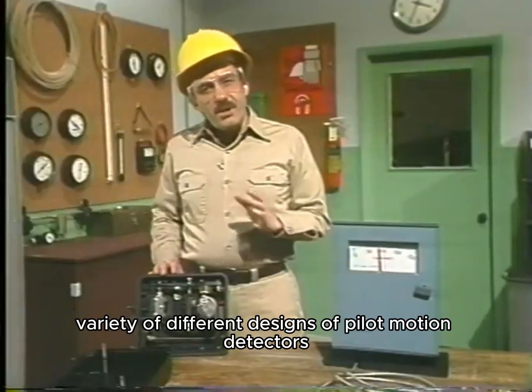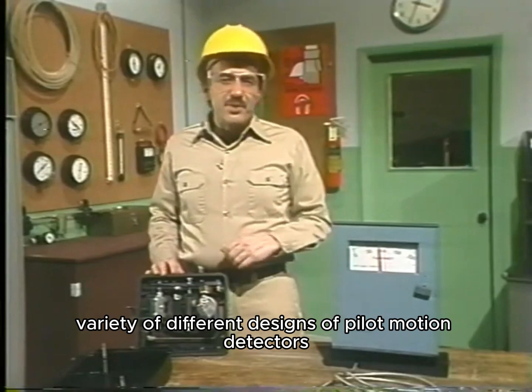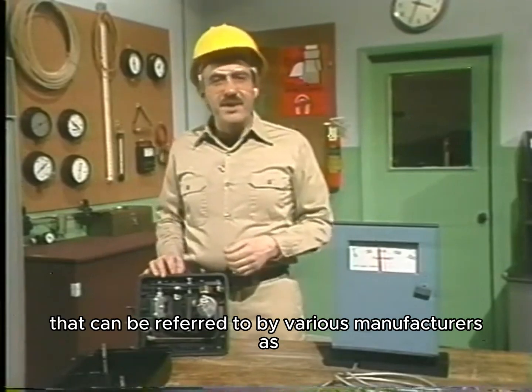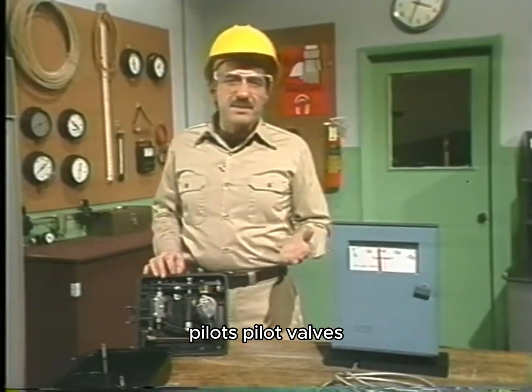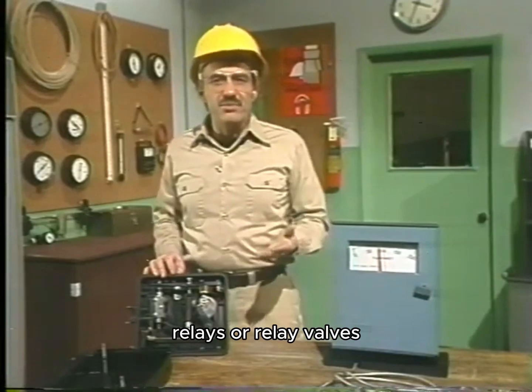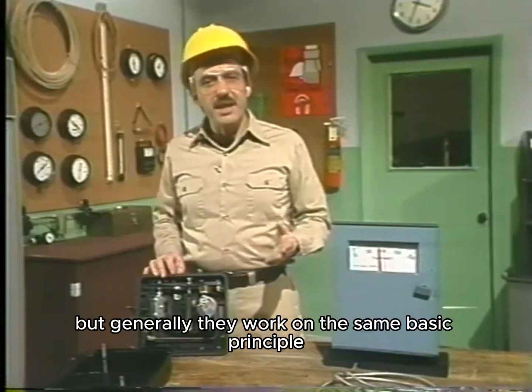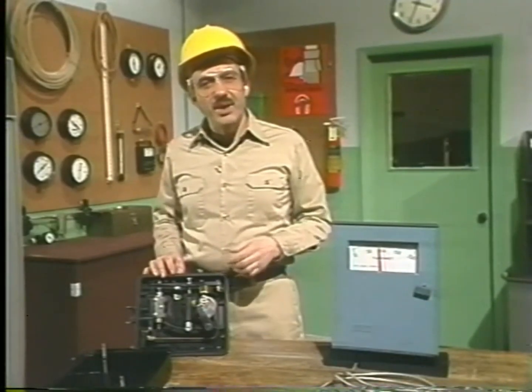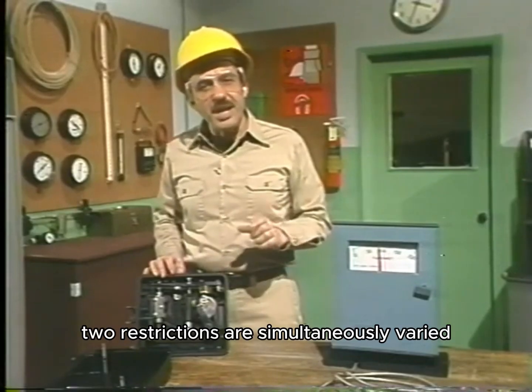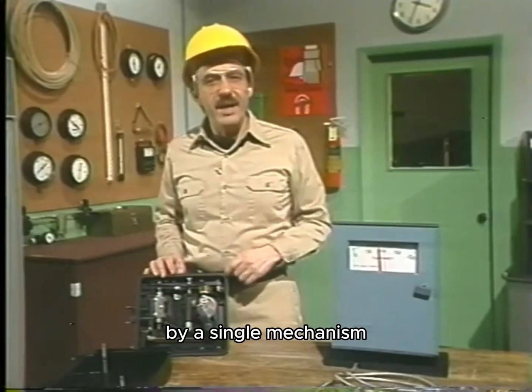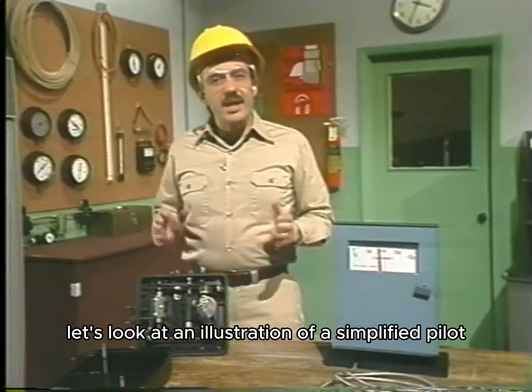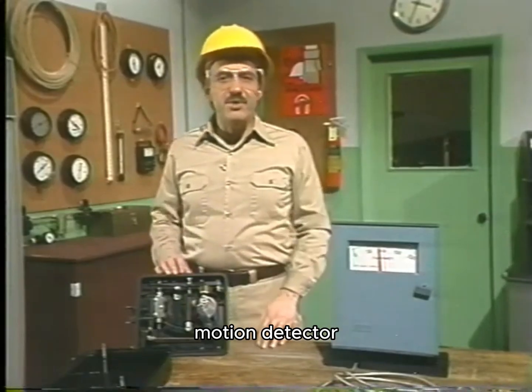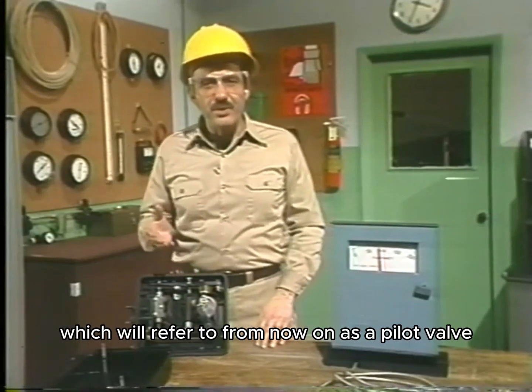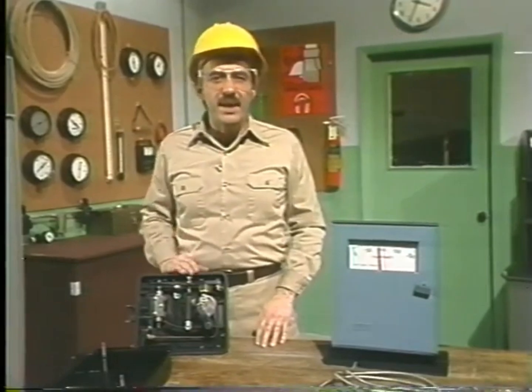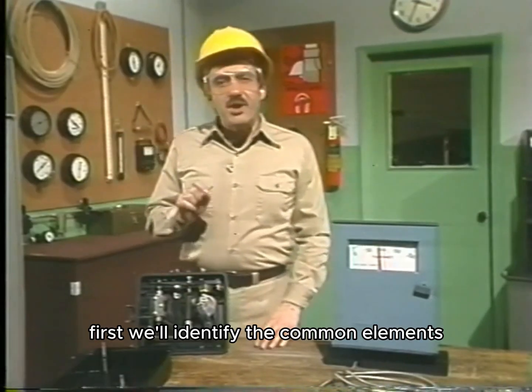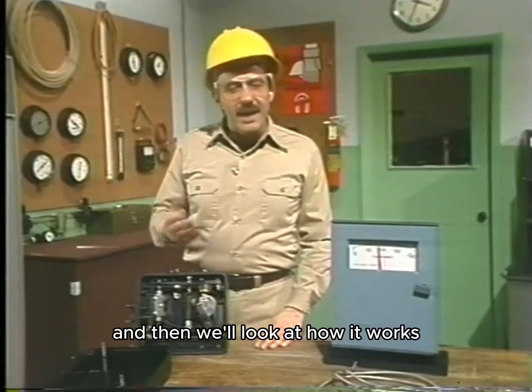Now, there are a variety of different designs of pilot motion detectors. They can be referred to by various manufacturers as pilots, pilot valves, relays, or relay valves. But generally, they work on the same basic principle. Two restrictions are simultaneously varied by a single mechanism. Let's look at an illustration of a simplified pilot motion detector, which we'll refer to from now on as a pilot valve. First, we'll identify the common elements, and then we'll look at how it works.